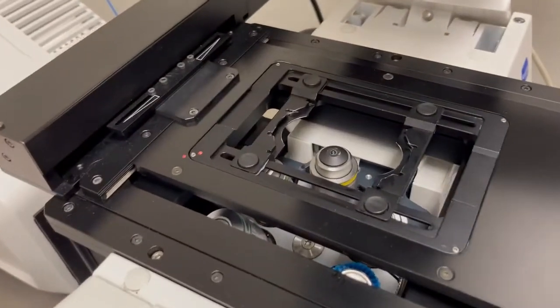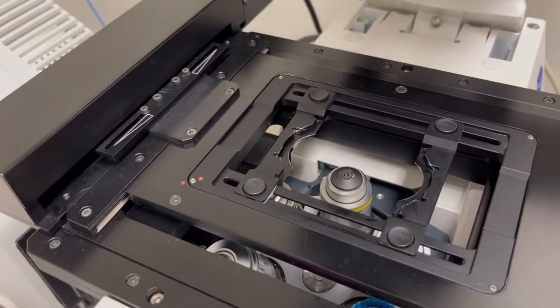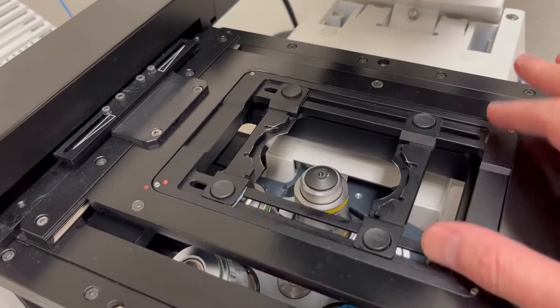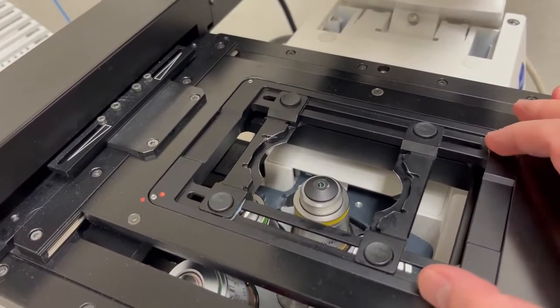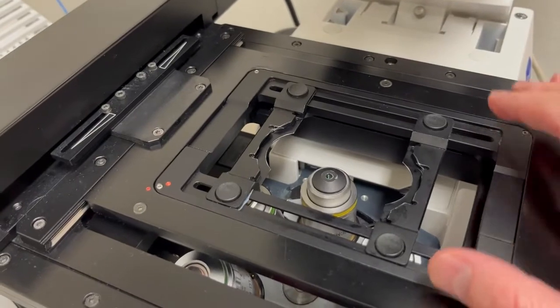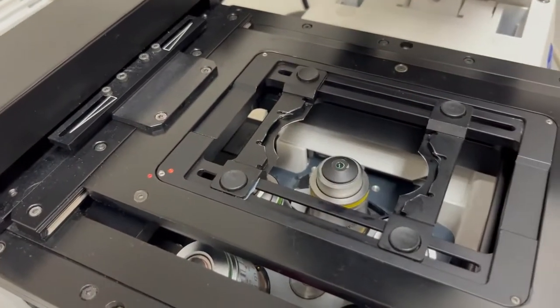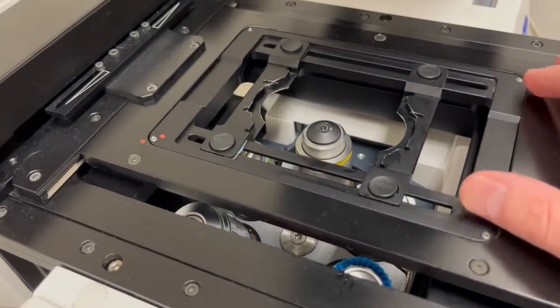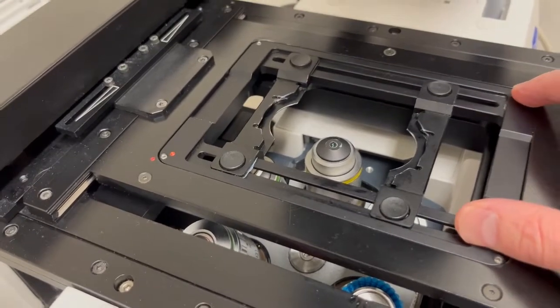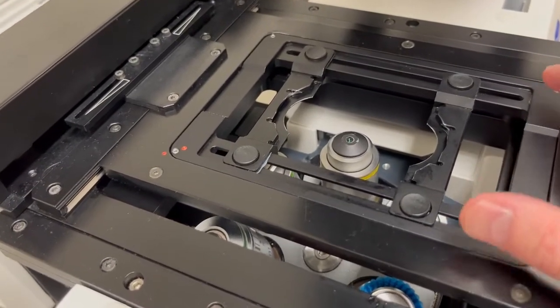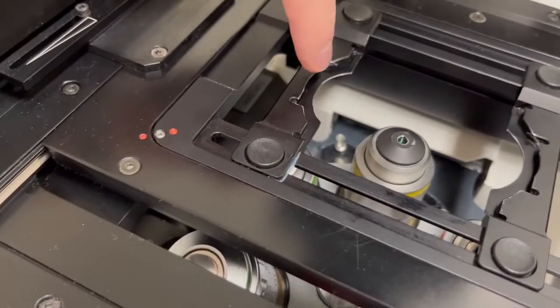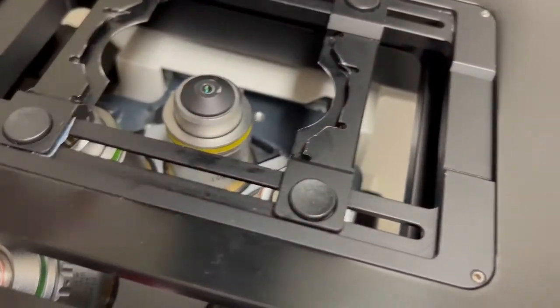The reason I recommend you do this is the 10x is one of our shorter objectives, and so this gives us room to check whether this is in the proper position, lowering the risks of banging this into an expensive piece of metal and glass. So what you want to do is check that this is level, that it's not moving, and that it's clean. You want to check these rims here, which is where your sample is going to go.